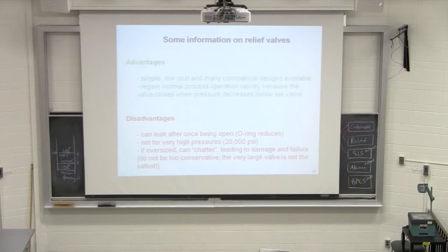So I've said several times already in this course that there's that two-week or one-week maintenance period in your plant. And one of the other things that happens, not only are you defouling, you're getting instrumentation technicians in. And they're going through every single valve and instrument and recalibrating it. Relief valves, they check that the pressure setting is at the correct rate, that there isn't corrosion. That's really, really critical, because corrosion can entirely eliminate the value that a safety valve provides. Right? And so they're checking it for all these issues and then making sure that the safety rating is still correct.